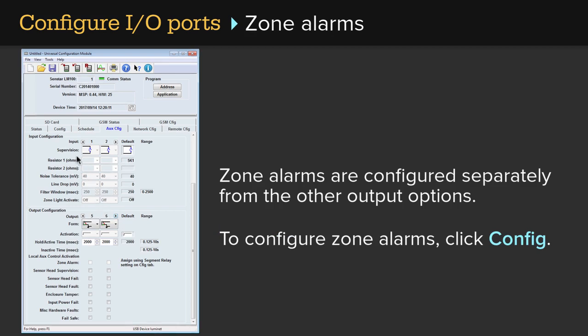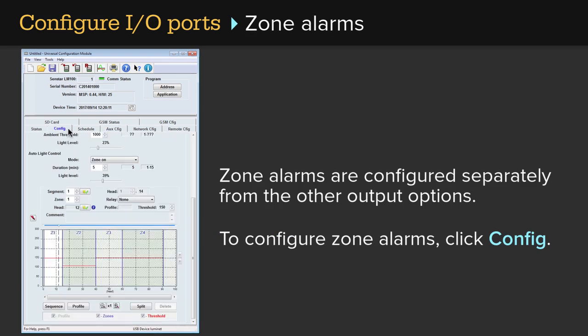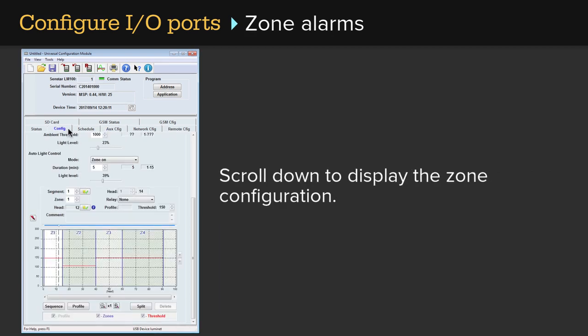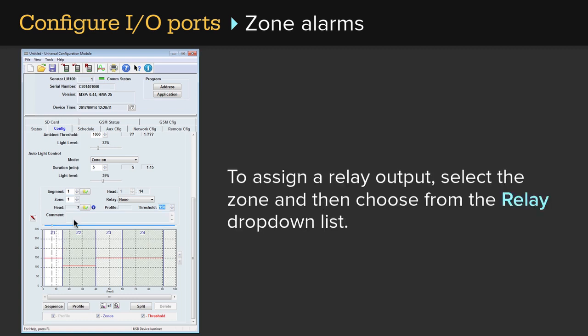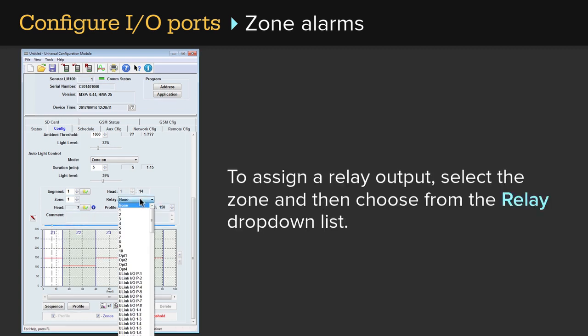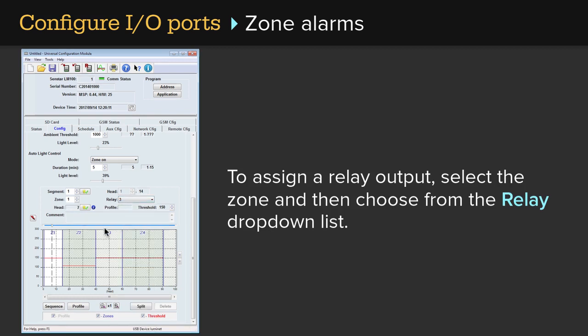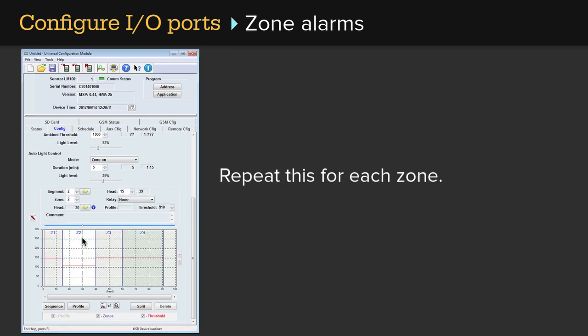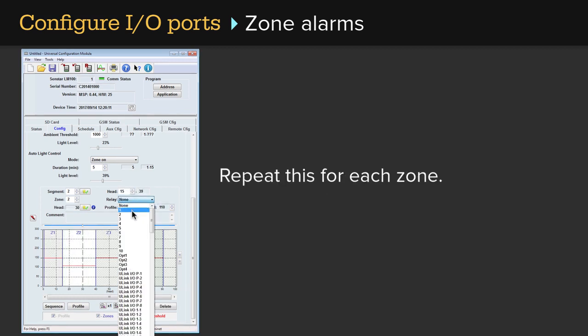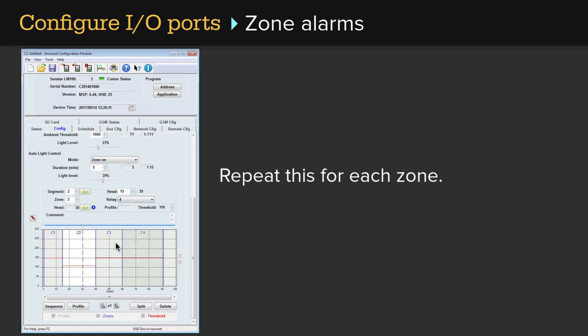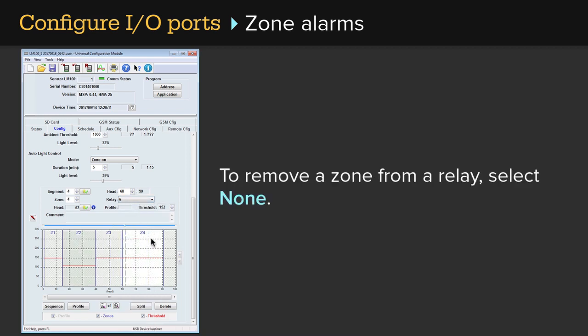Zone alarms are configured separately from the other output options. To configure zone alarms, click Config. Scroll down to display the zone configuration. To assign a relay output, select the zone and choose from the relay drop-down list. Repeat this for each zone. To remove a zone from a relay, select None.